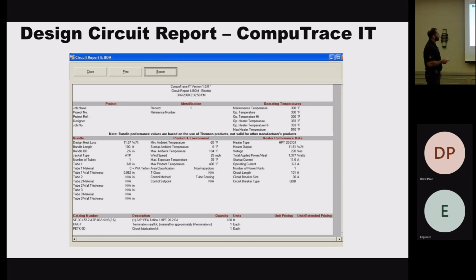Where's the voltage? At 220 volts. To get to 300F on the hottest day, that heater is going to get to 393F. Say this isn't general purpose and it's a class 1 div 2 T3 rated area. T3 is 392. This software will say, nope, you can't do that, you need a controlled design. So it sets a high temperature alarm to make sure that heater cable doesn't violate that T rating. That's something unique we have.